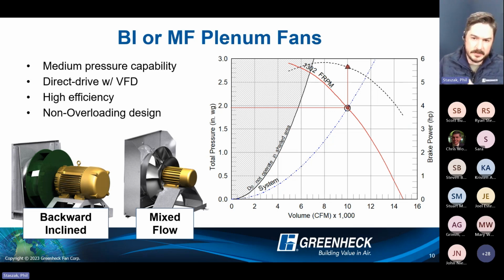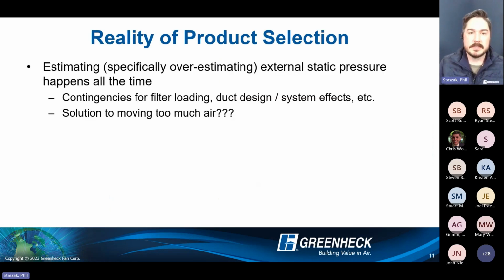Now that same scenario exists in this case, where 1/2 inch of static pressure maybe doesn't exist. Well, we're moving more airflow than design, right around that 12,000 CFM, but the fan curve and the brake horsepower curve kind of breaks the standard laws that we're used to. Believe it or not, we're moving more airflow than design with less resistance, but we're actually moving less brake horsepower. So it can easily be balanced. You're not in that overload state. You're actually operating less overall brake horsepower, and a test and balance guy can easily get in there and dial that system back to that design 10,000 CFM. So it's a non-overloading design.